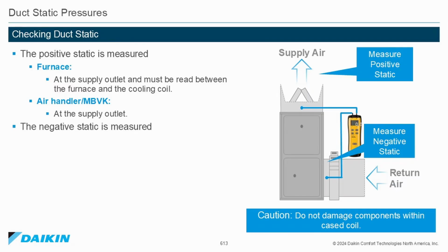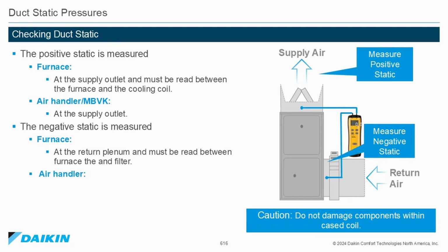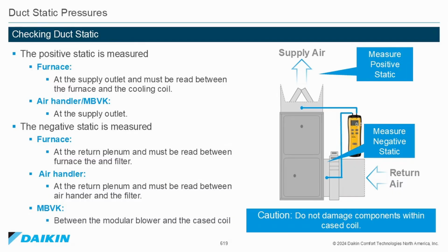The negative static pressure is measured on a furnace at the return air plenum and must be read between the furnace and the air filter. On an air handler, at the return air plenum and must be read between the air handler and the air filter. On the MBVK, between the modular blower and the cased coil. Be careful to not damage the components within the cased coil.